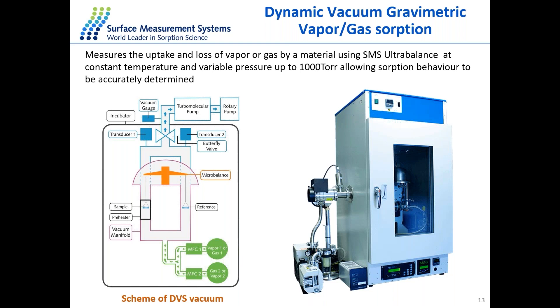The DVS Vacuum measures the uptake and loss of vapor by material using a balance at constant temperature and variable pressures up to 1000 Torr, allowing the adsorption behavior to be accurately determined. On the right-hand side, we have a picture of the DVS Vacuum analyzer; on the left-hand side is the schematic of the DVS Vacuum.